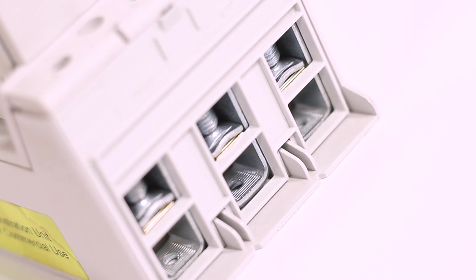Okay, and the other thing is obviously the coil voltage at the top. It seems a wider coil range. Can you explain that in a bit more detail as well? Yeah, so instead of having multiple options for coil ratings, we've got four, with or without PLC interfaces. So for example, a 24 volt AC option was separate to a 24 volt DC option. They're now the same coil, and that goes all the way through to 60 volts. Brilliant. So you're holding one product rather than maybe two, three or four that you might be holding in your stores.